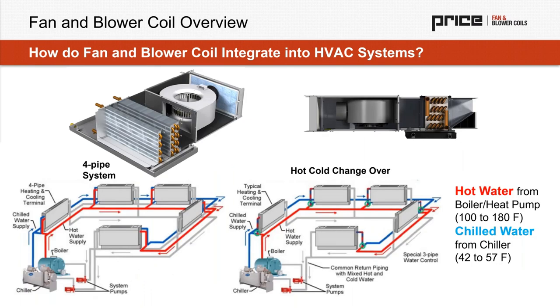The other way we can consider integration of the fan coil into the HVAC system is the hydronic side. And the hydronic side is becoming continually more constrained as we see supply hot water temperatures dropping with the use of heat pumps and heat recovery chillers. And as we see chilled water temperatures rising as well, as we're trying to reduce the lift of systems. So the supply fluid temperature in comparison to the ambient outdoor temperature, as we see that drop, our system lift is lower and it generally runs with a higher coefficient of performance. Those constraints mean we need to be more considerate of how we design and apply the hydronic system within buildings.